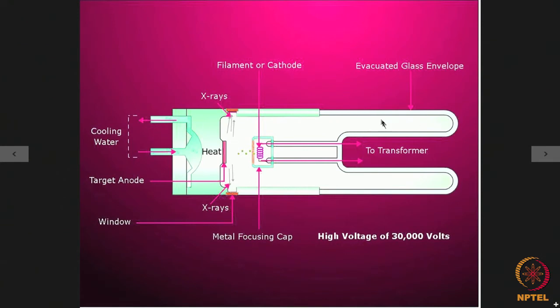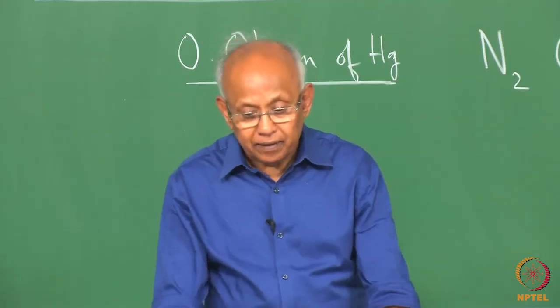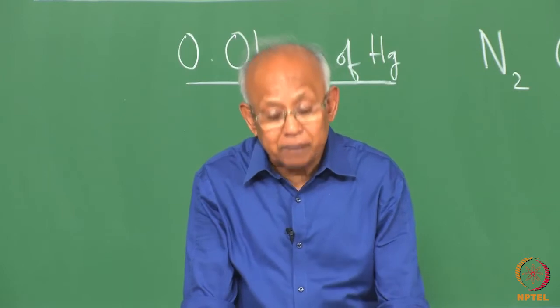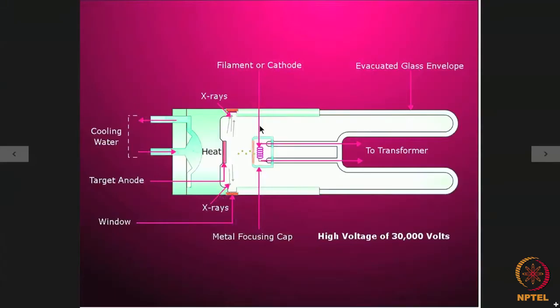The entire tube here is an evacuated glass envelope. The level of evacuation is pretty high. These windows through which the x-rays are let out are made up of low atomic number material such as aluminum, beryllium or even mica. This target gets heated up due to the impact of the striking electrons and there must be a method by which this can be cooled down by passing cooling water to the system.